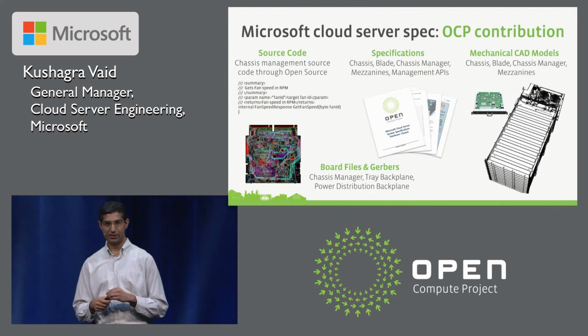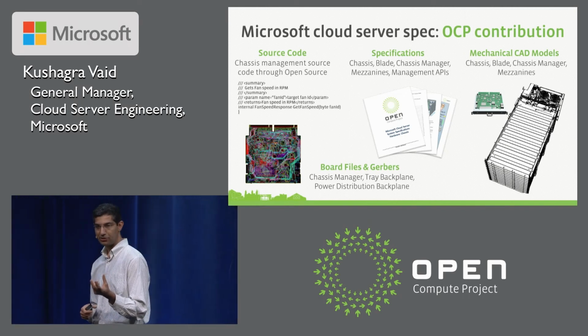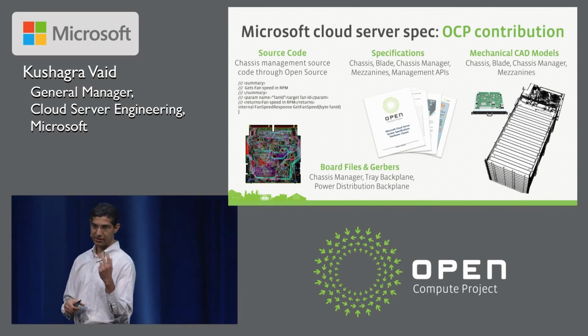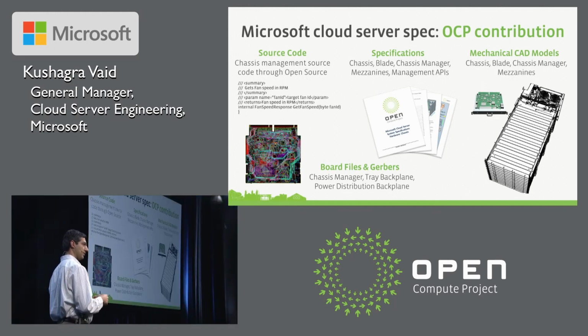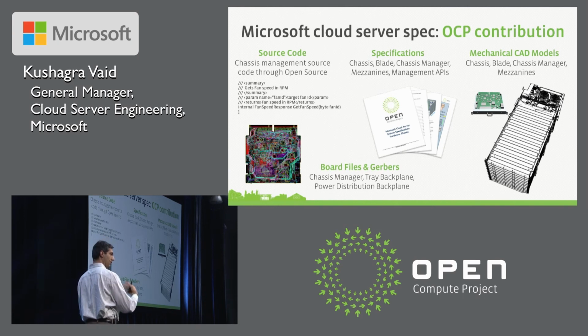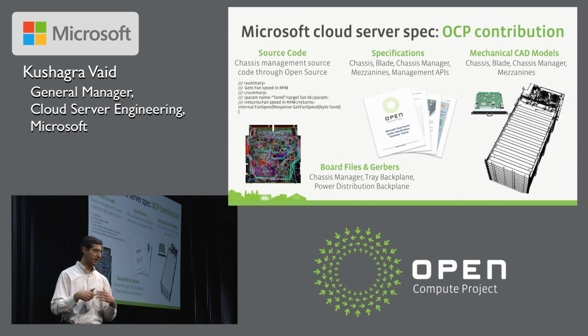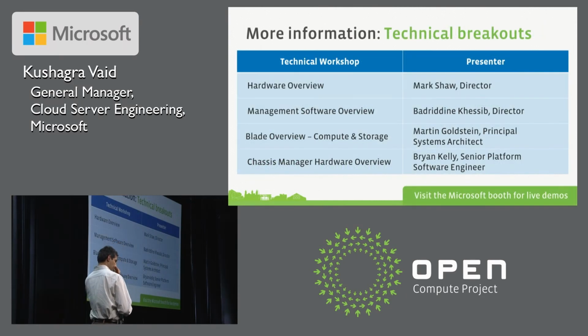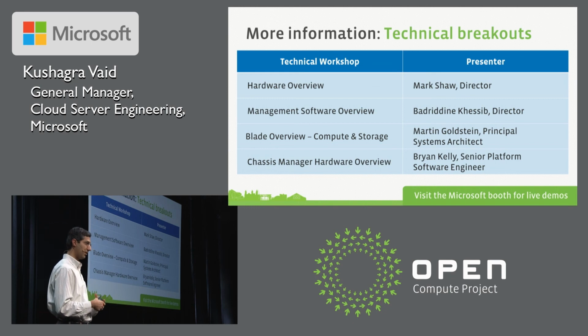The fourth thing is the source code for the chassis management. So the software that I mentioned, which runs on the chassis manager, does things like fan control, power supply management, blade management for blade on and off, the REST API, security, all those pieces. We'll be putting it on GitHub, and we'll be working with OCP to have an open source project to work with the community on improving and enhancing the functionality. So that's the contribution from Microsoft to Open Compute. We are very excited about joining OCP and look forward to working with the community in advancing the design and sharing our learnings from operating at a million server scale.